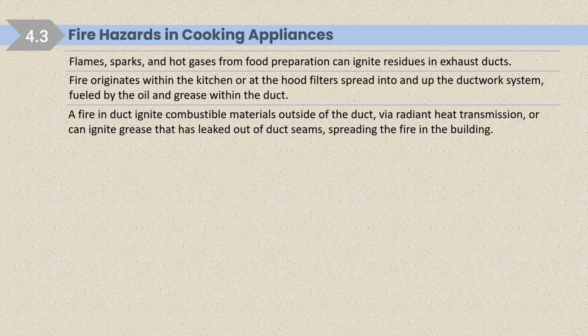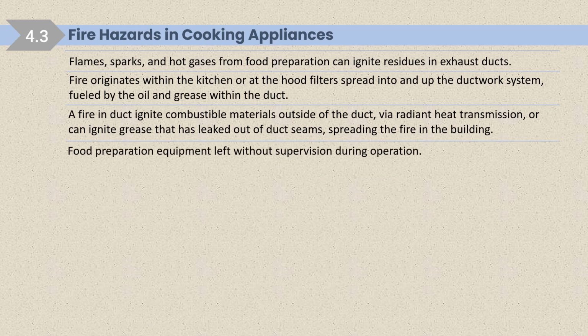Suppose the duct is not protected properly and it is in contact with combustible material, it can set fire to that combustible material through radiant heat transmission, or can ignite grease that has leaked out of the duct seams. Suppose the duct is not properly sealed, and there is some leakage near the seams that causes a fire, spreading the fire in the building.